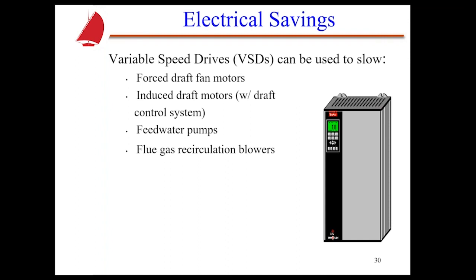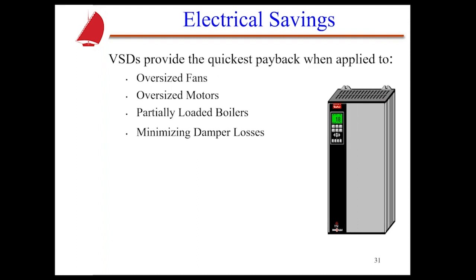For many, many years in this industry, people would buy a variable speed drive and they would buy the ability for bypass switching, if you will, because variable speed drives had some reliability issues. That is becoming less and less of an issue as the reliability has gotten better. And that's the reason that they're being selected as an option more and more also. The payback comes in when you're applying it because of, for instance, oversized fans, or an oversized motor is used, or if you've got a partially loaded boiler. So it can actually minimize damper losses. But one of the side things that I've always heard in the boiler room is the boiler operators just say, man, it's so much quieter in here. And it's just kind of a side benefit. Variable speed drives are very popular and they will save a lot of money on power.